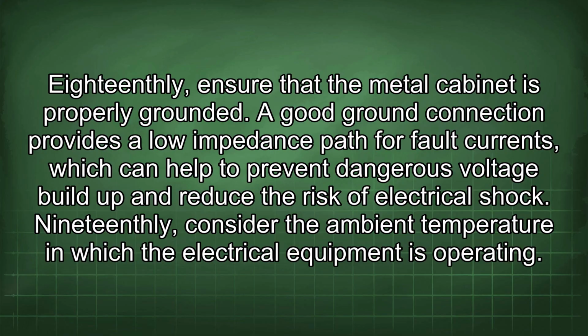Eighteenthly, ensure that the metal cabinet is properly grounded. A good ground connection provides a low impedance path for fault currents, which can help to prevent dangerous voltage build-up and reduce the risk of electrical shock.